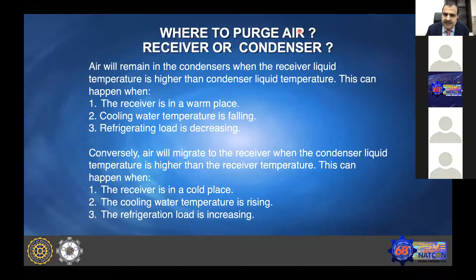One more condition which we have to know: variation in the refrigeration load also decides the condenser and the receiver temperatures. So if the refrigeration load is decreasing from the rated condition, then it may happen that the condenser has a lower temperature than the receiver. And if the refrigeration load is increasing, then the condenser may be at a higher temperature than the receiver. So purging points should be taken from both, connected to the air purger.